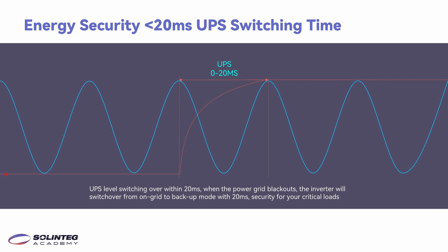For the grid frequency, usually 50 Hz or 60 Hz. For 50 Hz, that means in 1 second we will have 50 grid cycles. So each cycle is 20 milliseconds. The inverter will switch from on-grid to off-grid if it doesn't detect half of a cycle, which is 10 milliseconds. It also takes some time for the relay operation. That's why we need less than 20 milliseconds to switch between on-grid and off-grid.